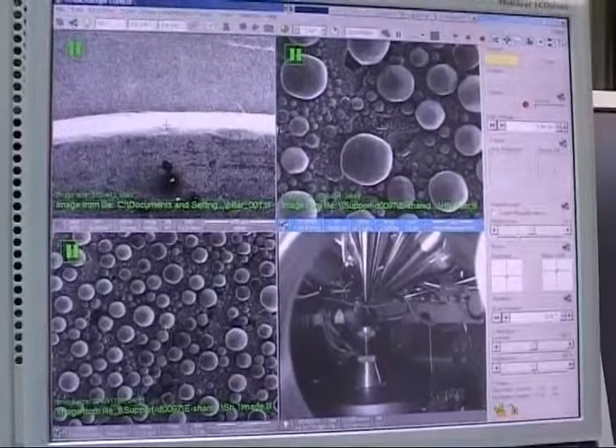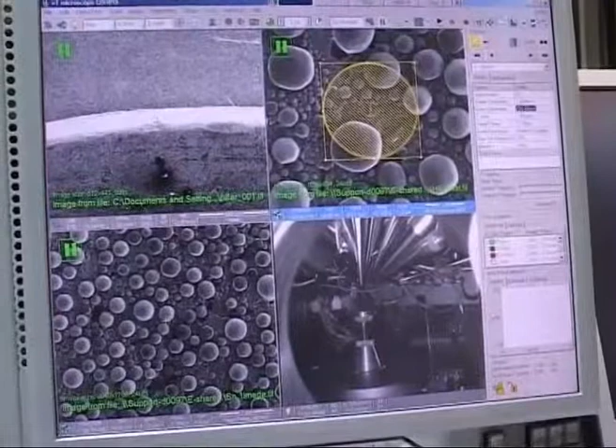When you have to pattern some image, you just select whatever kind of pattern you want to mill. Let us say a rectangle, just select the rectangle, and then when you select the beam current, it shows the time available for milling. You select here the X, Y and Z dimensions of the pattern to be milled or deposited on some substrate, and we can also select polygon, circle, line. Suppose we have selected a circle; its dimension we can give, and the inner diameter we can give. If we give some inner diameter, then it will be an annular ring. So you can give inner radius and outer radius, so that you can mill the way you want. Here you can see that it is like an annular ring, where the inner diameter is 200 micron and the outer is 1200 micron.